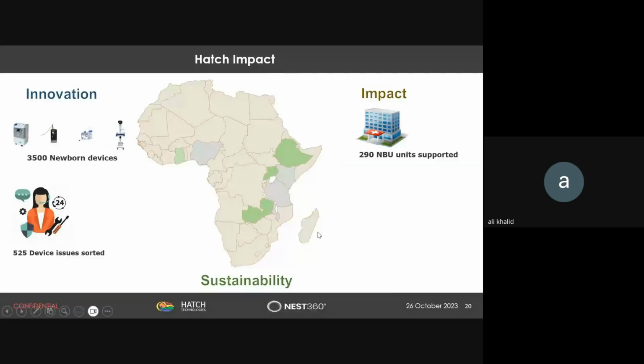If I pick up the question on why we are only monitoring temperature and perhaps humidity, first of all, we are measuring the utilization, the device utilization. I don't know if you got that. So the sensor is able to measure the device utilization of the device. Then the second thing is we're asking ourselves, are there any environmental issues that happen in the newborn unit? This could be in the form of high humidity, or high temperatures, or, let's say, in those areas which experience winter, very low temperatures. Those are the ones we're able to monitor.